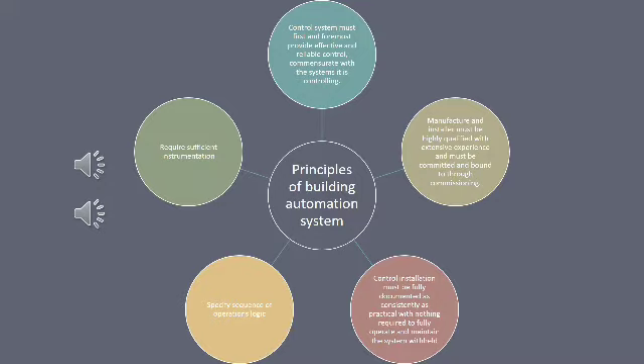It requires sufficient instrumentation. The designer needs to define the instrumentation requirements to support the sequence of operation of the building, and also data acquisition capability to support equipment performance monitoring and building diagnostics and analysis. In order to establish the instrumentation requirements, it must include the specification of the product or the system itself. With an accurate specification, the design and function of the building can meet the required standard. This identifies, at a minimum, the common types of instrumentation in use in the system.